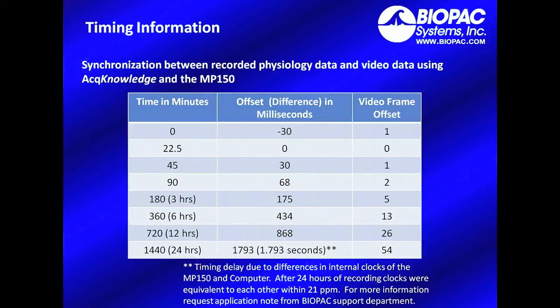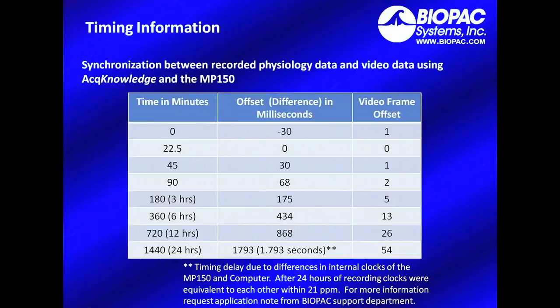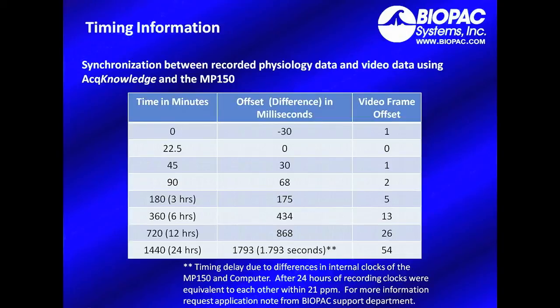After 24 hours of recording, there was a 1.793 second offset, or difference, which corresponds to about 54 video frames. This timing delay is due to differences in the internal clocks of the MP150 system and computer. For more information, you can request the application note from the Biopac Support Department.